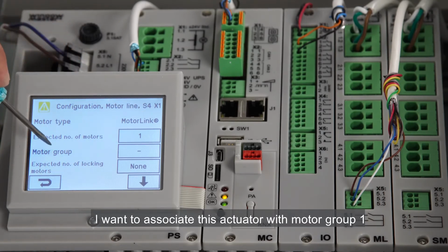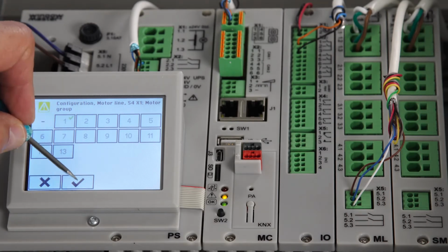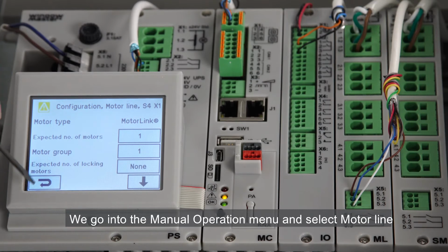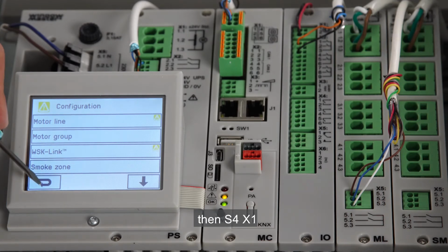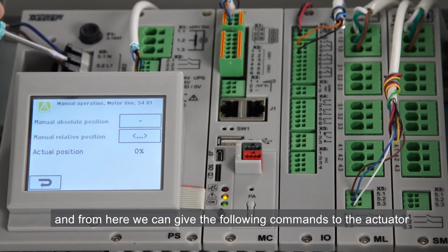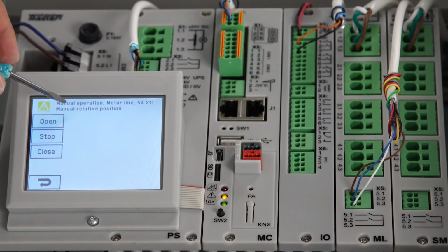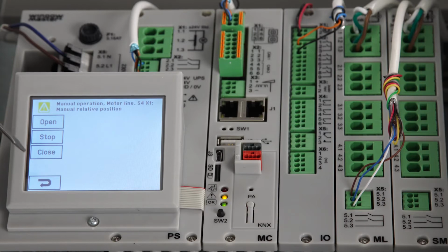I want to associate this actuator with motor group 1. I select 1. We can test the motor line from the screen. We go into the manual operation menu and select motor line, then S4X1. We select manual relative position, and from here we can give the following commands to the actuator. Open, stop, and close to check that it's running.